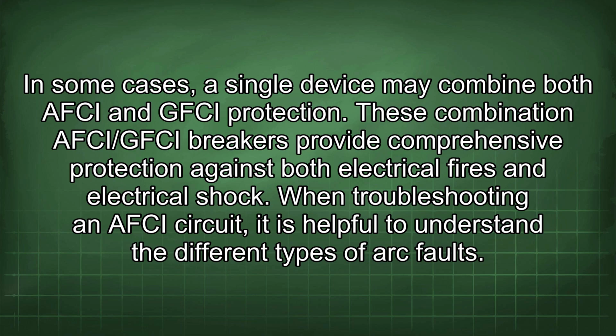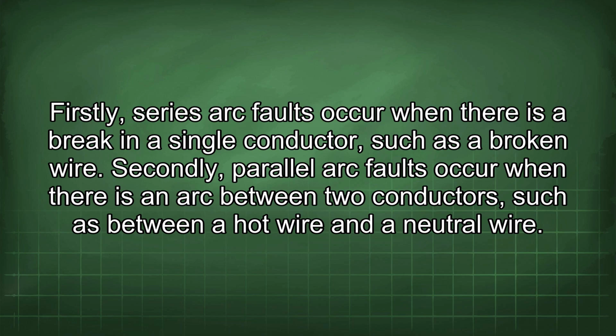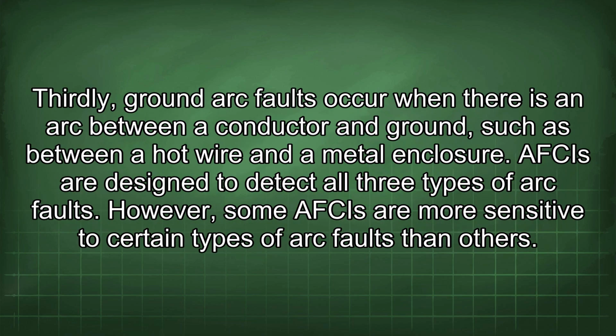When troubleshooting an AFCI circuit, it is helpful to understand the different types of arc faults. Firstly, series arc faults occur when there is a break in a single conductor, such as a broken wire. Secondly, parallel arc faults occur when there is an arc between two conductors, such as between a hot wire and a neutral wire. Thirdly, ground arc faults occur when there is an arc between a conductor and ground, such as between a hot wire and a metal enclosure. AFCIs are designed to detect all three types of arc faults.